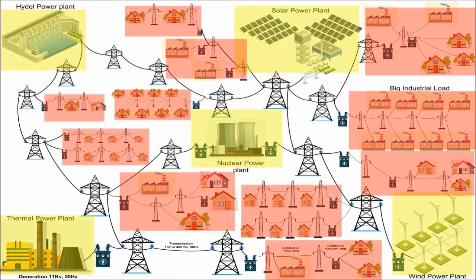Despite all these precautions, sometimes the complete system fails to maintain synchronization among generating units and load centers, and load demand exceeds the energy reserve at that instant and sometimes exceeds the total capability of the system, and consequently overloads all generating units. In such cases, firstly, the weak generating unit would fail and its load gets distributed among the remaining units, resulting in more overloading of the remaining units. This may start a chain reaction and one by one generating units go off grid by their own overload protection switchgears. This way the whole system gets shut down and we can say the grid has failed.